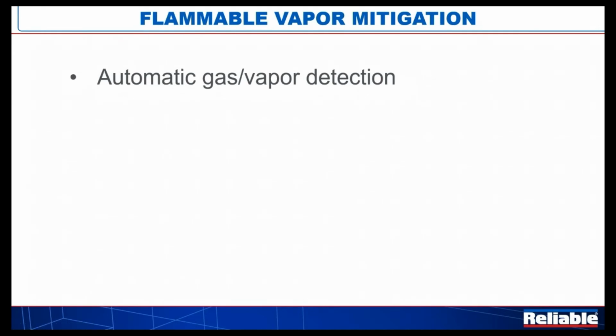And then finally, again, just a small section on flammable vapor mitigation. I got to thinking about this morning, well, if you have it, it's pretty catastrophic. But I'm just imagining that there's probably a need every once in a while to emergency vent these tanks. And let's just say it's a heavier than air vapor, and we're going to put it in a containment pit. If we have to do that, or if it happens by accident, we want to make sure that we've got that adequately protected. So they give us some guidelines here.